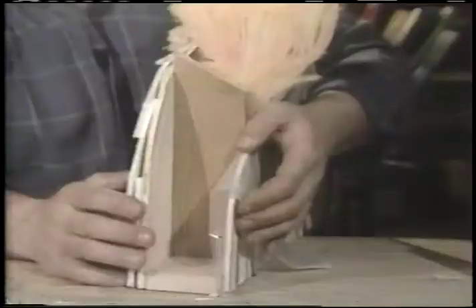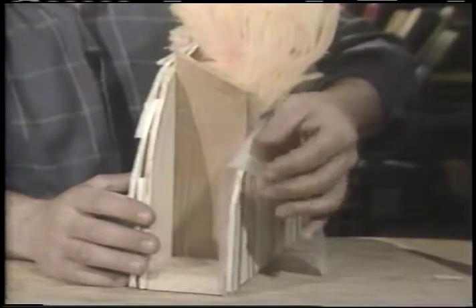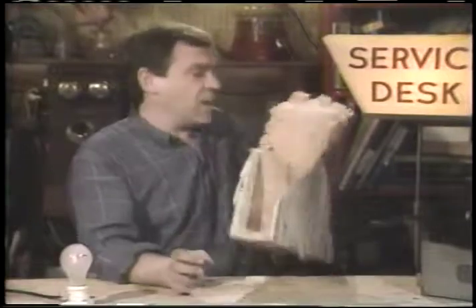Any warm air that does reach the cool surface would give up its moisture, the same as breathing on a cold window. So the wall assembly has a vapor barrier installed on the warm side to keep the household humidity from entering and rotting the wall. If cold outside air is allowed to blow right through this insulation, it doesn't do anything except trap dust.